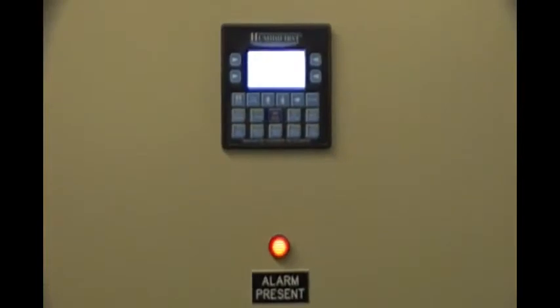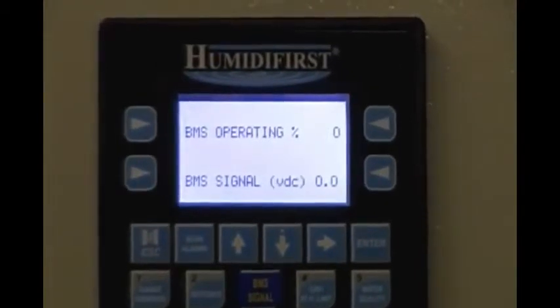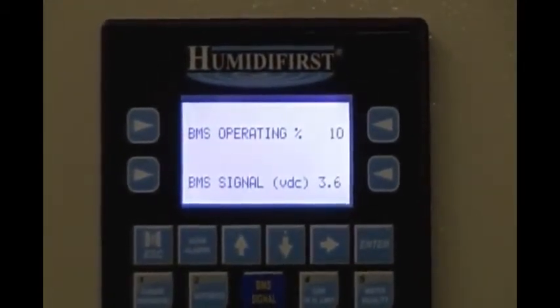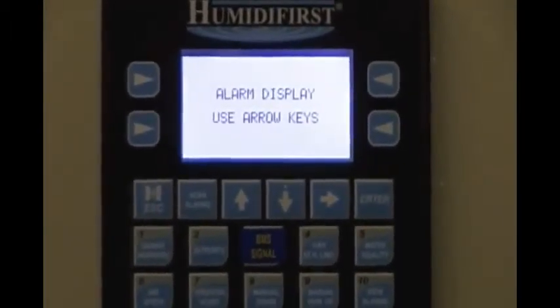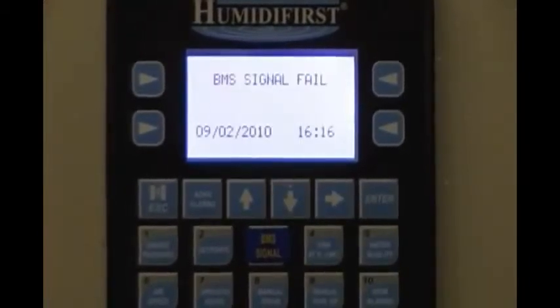Button number 10 is View Alarms. This allows you to see your alarms and erase them as they're triggered. I will now simulate a BMS signal failure. You will now notice your alarm present light indicator has been lit, and you'll notice the operating percentage of humidifiers has dropped to 0. We'll press button number 10, alarm display, use arrow keys, and you can scroll down to your alarm.